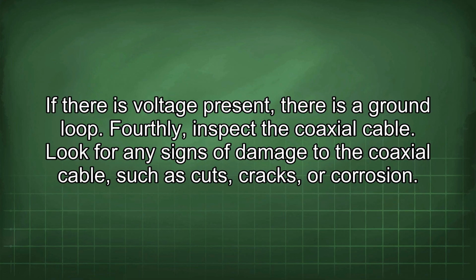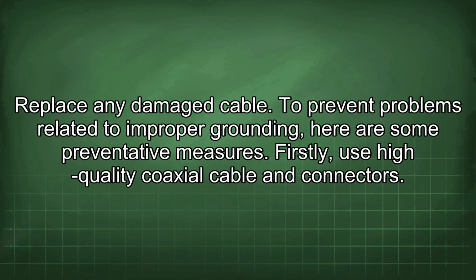If there is voltage present, there is a ground loop. Fourthly, inspect the coaxial cable. Look for any signs of damage to the coaxial cable, such as cuts, cracks, or corrosion. Replace any damaged cable. To prevent problems related to improper grounding, here are some preventative measures.